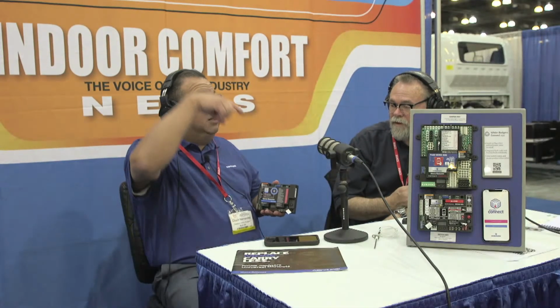A lot of older controls provided spark ignition, but the thermostat had to be run down to the floor. This control has a built-in thermostat, and this little blue device you see on all three is a Bluetooth adapter. So if I plug in a Bluetooth adapter, I can connect to it like I was touching it from 20 feet away. I don't have to get on a ladder to look at anything - I just get close, connect, and I'm looking at it.